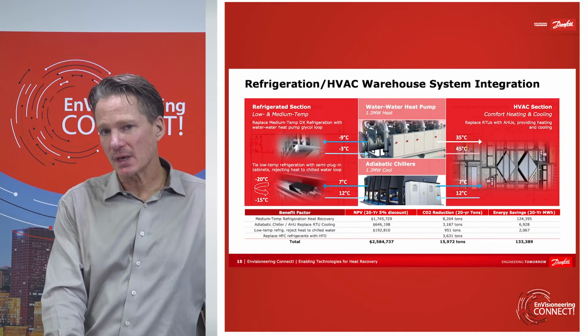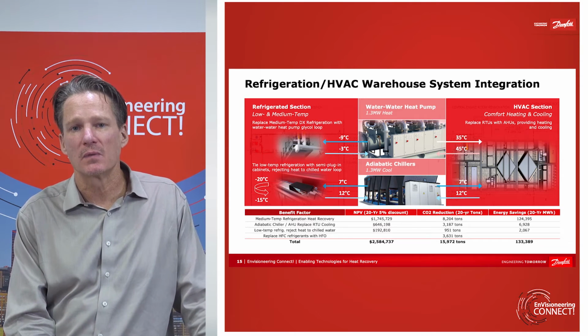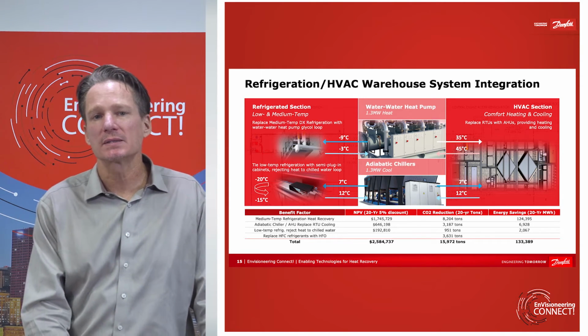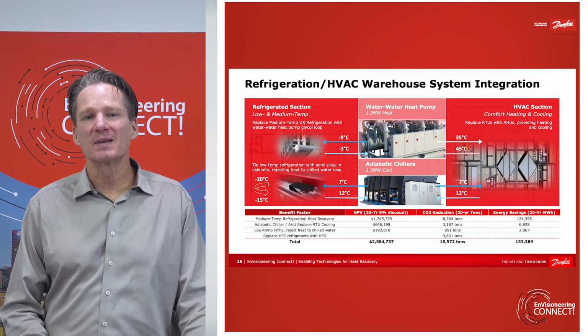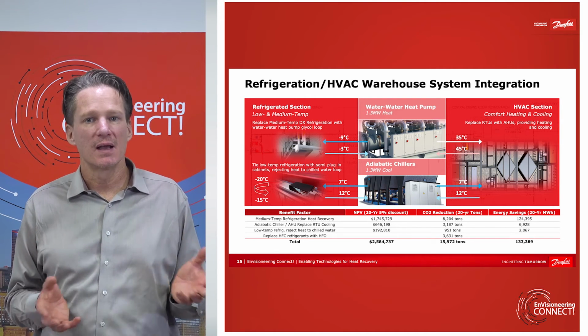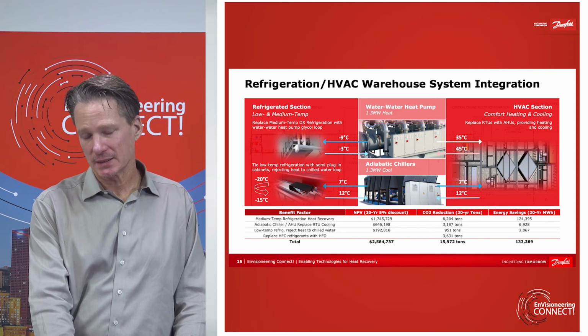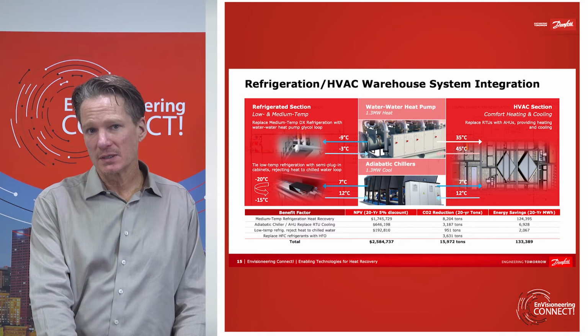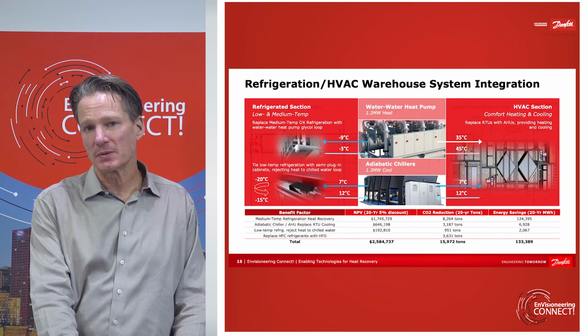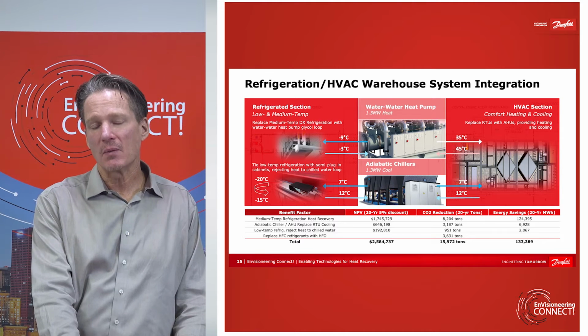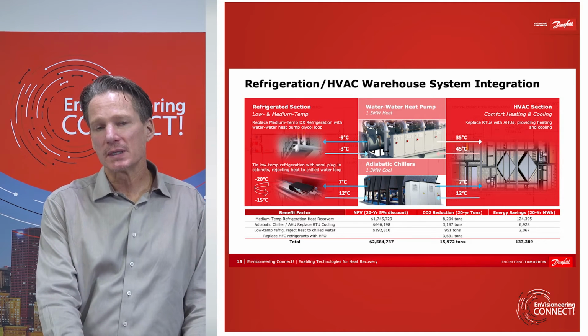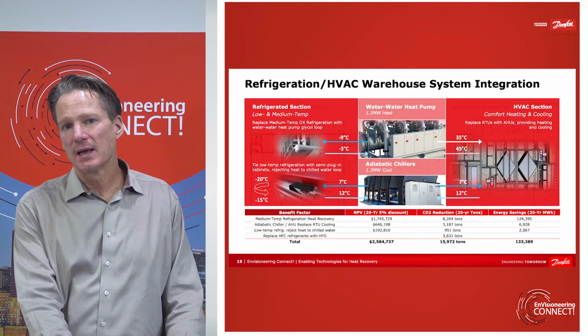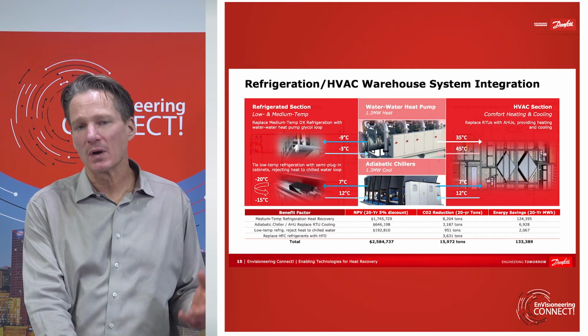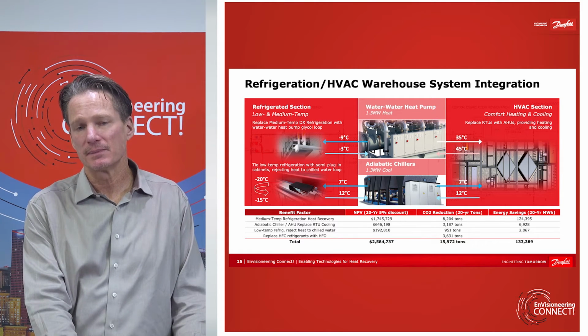This is another one that we worked on, electrification of a heating system for a consumer goods warehouse. And in this system, what we were doing was trying to integrate in their refrigeration and HVAC system. So how we did that was by taking the medium temperature refrigeration system that they had on that warehouse and tying it into a water-to-water heat pump, and then the low temp refrigeration system that they had and tying it into a comfort cooling water-cooled water chiller system.